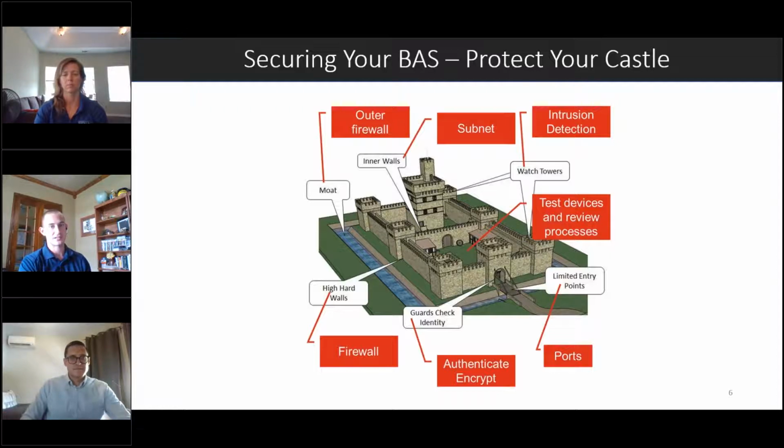So with an OT network, machine-to-machine communication is usually pretty consistent, whereas communication between IT devices like someone's laptop can vary. They may go from Outlook to a web page, and they may jump to YouTube and be streaming, so the network traffic can vary greatly. Whereas machine-to-machine communication is usually pretty consistent and very predictable. So it makes it a lot easier to monitor machine communication and look for anomalies or abnormalities that may be suspicious. And if you see something that looks suspicious, it's easier to pick it up quickly and either stop it or report it to someone to go look at it.